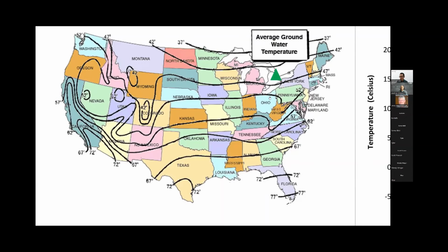And if I zoom into this figure, I haven't found a good one in North America, so I have to use the one for the States. So it's in Fahrenheit as well, but we see where we are located here. That stable ground temperature by that 30-foot depth is about 9 to 10 degrees Celsius across the year all around our area here in southwestern Ontario. So that's where the efficiency comes from.